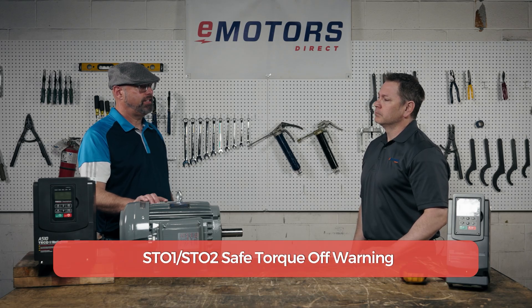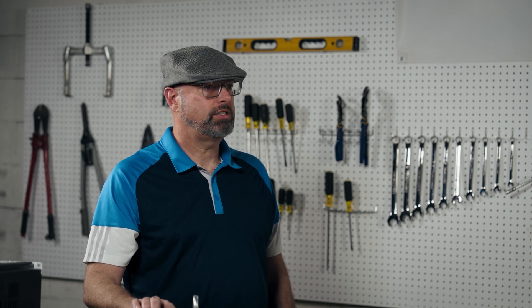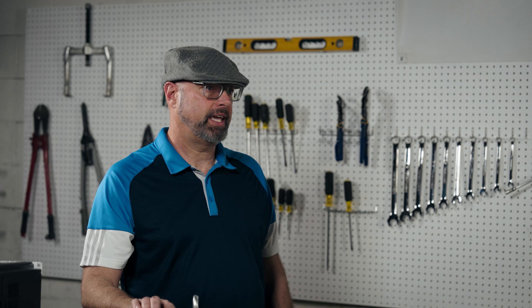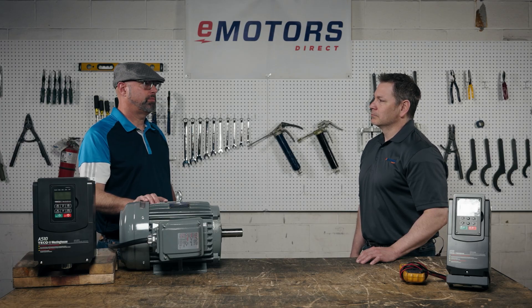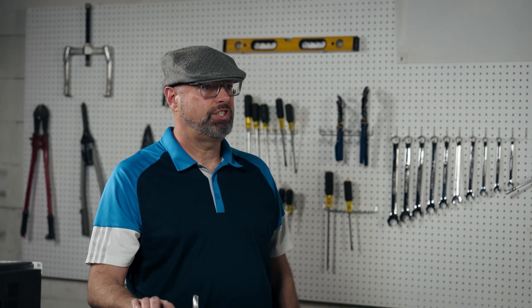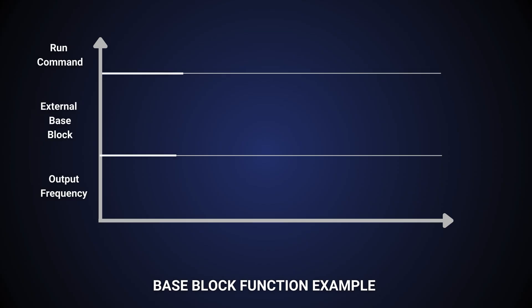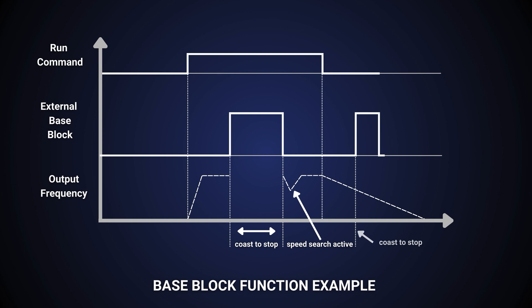STO1 and STO2 — safe torque off. The VFD will come with factory installed jumpers on SF1, SF2, and SG. These are to be used for a safe torque off application. It is common to see end users try to use these inputs as enables, but the trick is the VFD treats them like a fault that needs to be reset each time they are open. For an enable, I suggest using a digital input programmed to a base block function. A base block is when the VFD is in a state where it will not go into a run condition. There are some built-in protections such as too many consecutive overload faults in a short period of time. You can, however, program a digital input to activate a base block.